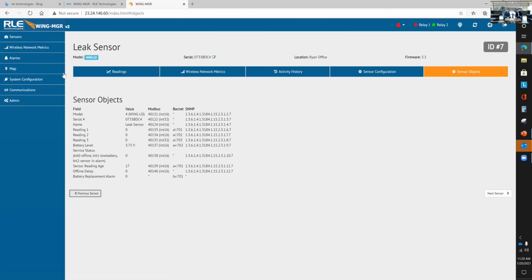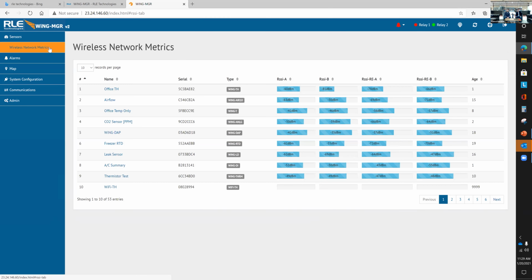So the other couple things to debunk concerns of wireless is with our 900 megahertz transmitters - every sensor also has wireless network health checking, just checking the health of the wireless network. It's a received signal strength indicator, letting us know how strong of a signal it is. When you typically start getting down to -80, -90 dBm, that's when you're looking at possibly using a...